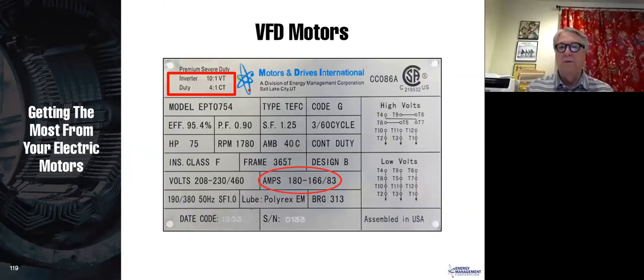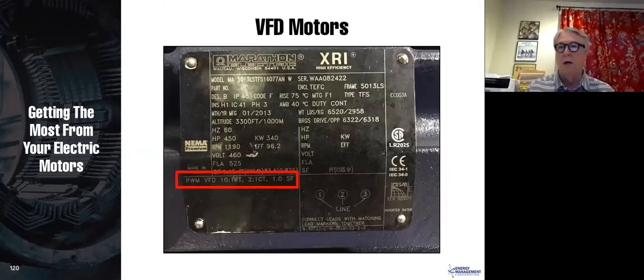Now here's another VFD motor nameplate. Notice up here it says on inverter duty, it can run over a 10-to-1 speed range variable torque or a 4-to-1 speed range constant torque. So you get different things on different nameplates, and clearly when you look at this, it's obviously an inverter duty motor. Now it doesn't say NEMA MG1 Part 31. That would be nice if it did, but again, different manufacturers put different things on the nameplate. The last nameplate didn't have the speed range that this one does.